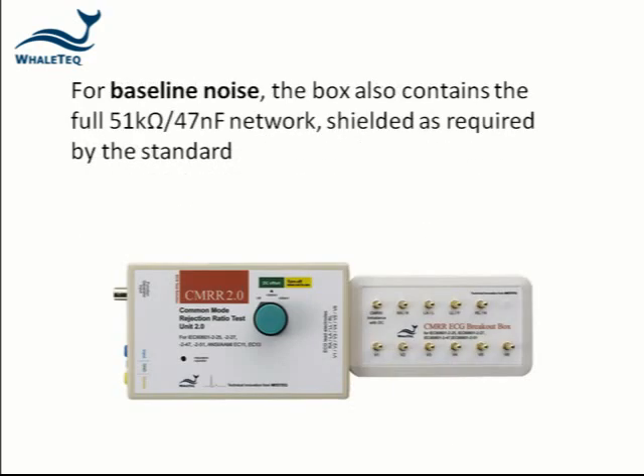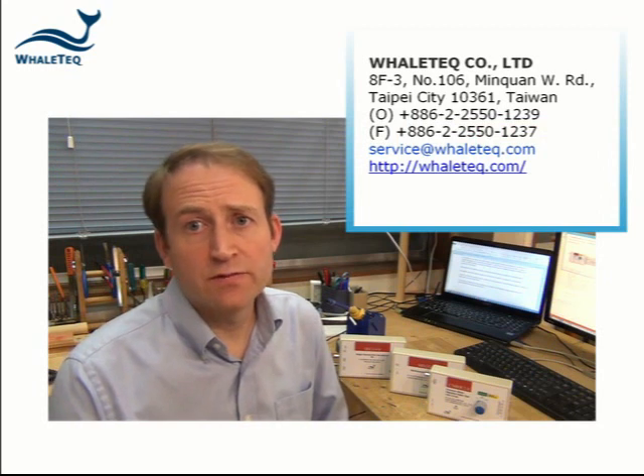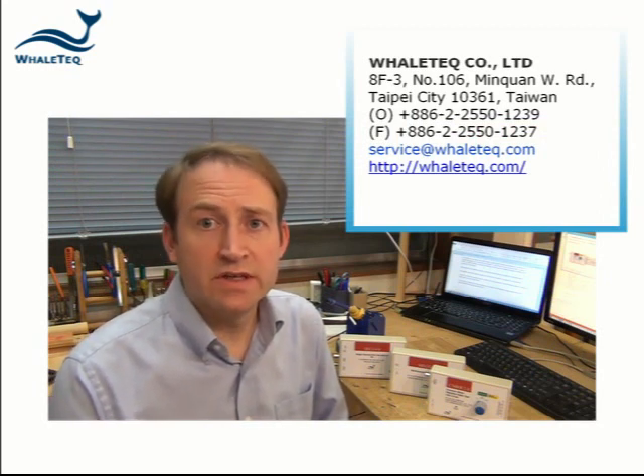For the baseline noise test, the box also contains the full 51k ohm 47 nF network as required by the standards. That's a brief introduction of the three items of test equipment with enough information to help you select which units suit your needs. If you have any further questions, please feel free to contact WhaleTeq using the details shown. Thanks for your time.